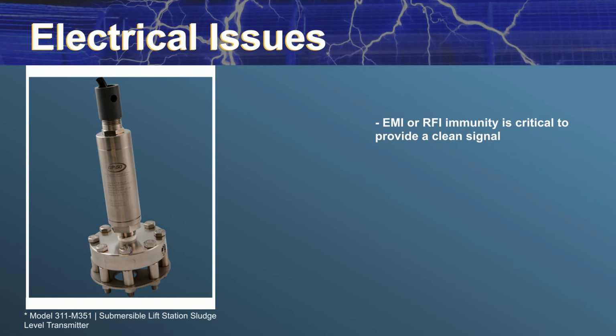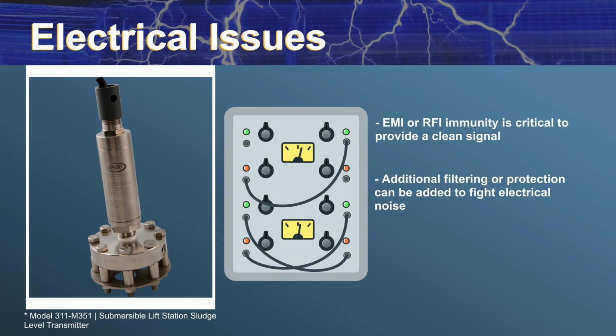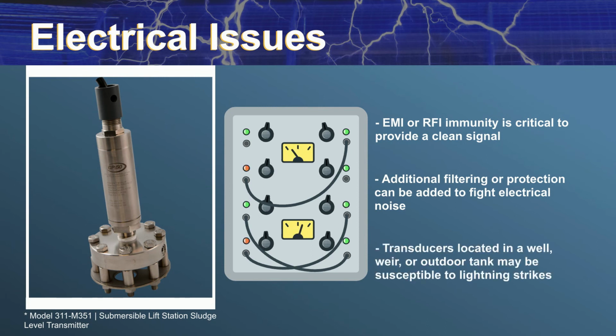For some applications, EMI or RFI immunity is critical to provide a clean signal. If there are known issues with electrical noise, GP50 can provide further filtering or protection of each unit. Lightning can also play a role in damaging a transducer. Many applications that require mounting a transmitter in a well, weir, or tank outdoors may be susceptible to lightning strikes. Providing internal surge protection as well as protection on the input line can greatly prolong the life of a transmitter that's mounted in lightning-prone areas.